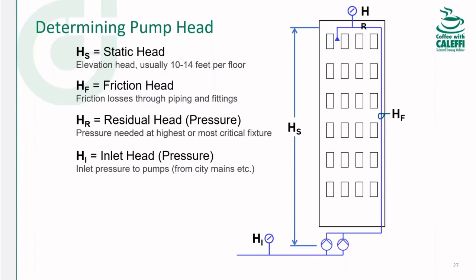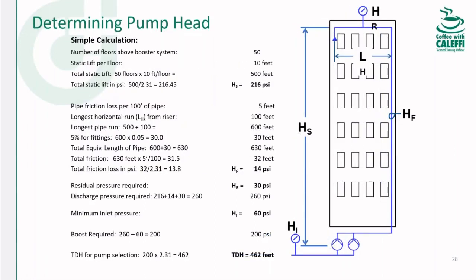And then last but not least, believe it or not, this is probably the one that's most easily forgotten. We've got the inlet pressure. So this is the pressure coming into the building before the pump. And a very important note, this is a dynamic value. So you want to take this measurement during a period of high flow demand because the pressure can drop at high flows. If you size it based off 80 PSI when there was no flow, and now you've got a high flow in the building and the inlet pressure drops to 40 PSI, you're going to have some problems because those pumps won't be able to keep up. Okay, and just for time's sake, we're not going to run through this example, but I'll leave it in the slide deck so you guys can reference that in the PDF.